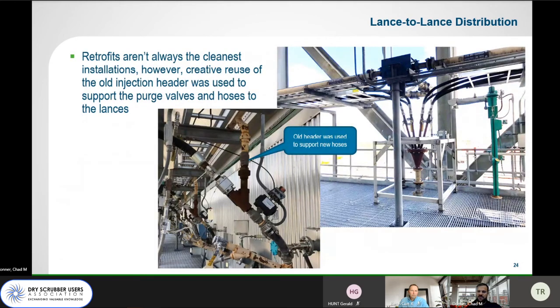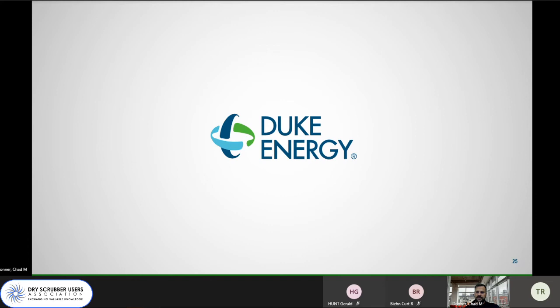And again, retrofits aren't always the cleanest, but here we were able to creatively use the existing header to help support and hold things and give us as clean and smooth an installation as possible. We would have liked to have had the purge lances relocated, but we're in the middle of weighing capital cost to complete the upgrade against benefit extracted. Ideally, you'd like to have purge lances located at your splitter so that you could purge the whole hose and down through the lance. But here, the purge lances are still located directly at the lance. I believe that is it. Any questions?